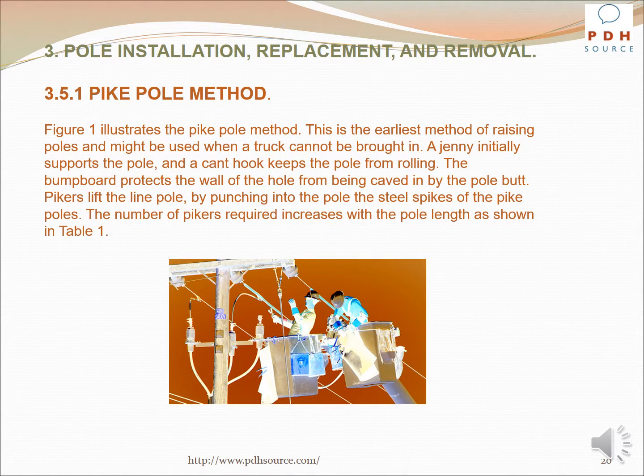Figure 1 illustrates the pike pole method. This is the earliest method of raising poles and may be used when a truck cannot be brought in. A jenny initially supports the pole and a cant hook keeps the pole from rolling. The bumpboard protects the wall of the hole from being caved in by the pole butt. Pikers lift the line pole by punching into the pole the steel spikes of the pike poles. The number of pikers required increases with the pole length as shown in Table 1.